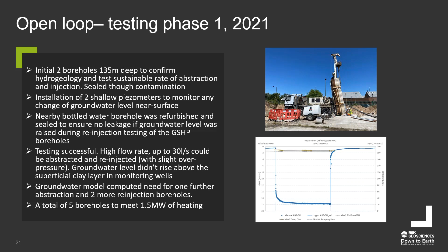So we had 2 boreholes. Those were drilled just before they started developing the site. The next 3 boreholes were then drilled as they were starting to develop the site, and that site became extremely busy, to say the least. The additional 3 boreholes were also drilled to a depth of 135 metres with steel grouted casing through the sediments above the chalk, and about 5 metres into the top of the chalk to seal off everything above.